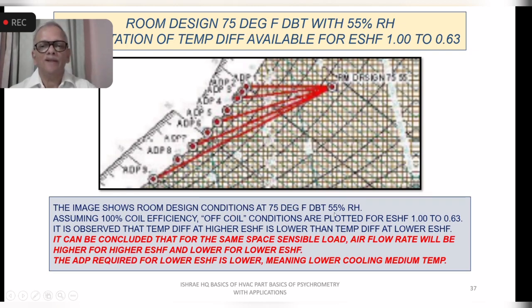So the image is showing the room design at 75-55. I am assuming 100% coil efficiency. ISHRAE says 90%. Carrier says you have to use the bypass factor calculation and then determine that leaving point or off coil condition. And these are plotted for 1 to 0.63, all these ADPs. Now you can check as the sensible heat factor goes lower from 1 to 0.63, you will see the inclination is increasing, which shows that the amount of latent heat or moisture removal is increasing. There is a reduction in the sensible heat to be removed, and the latent heat or the moisture content to be removed is increasing. And that's why that slant.